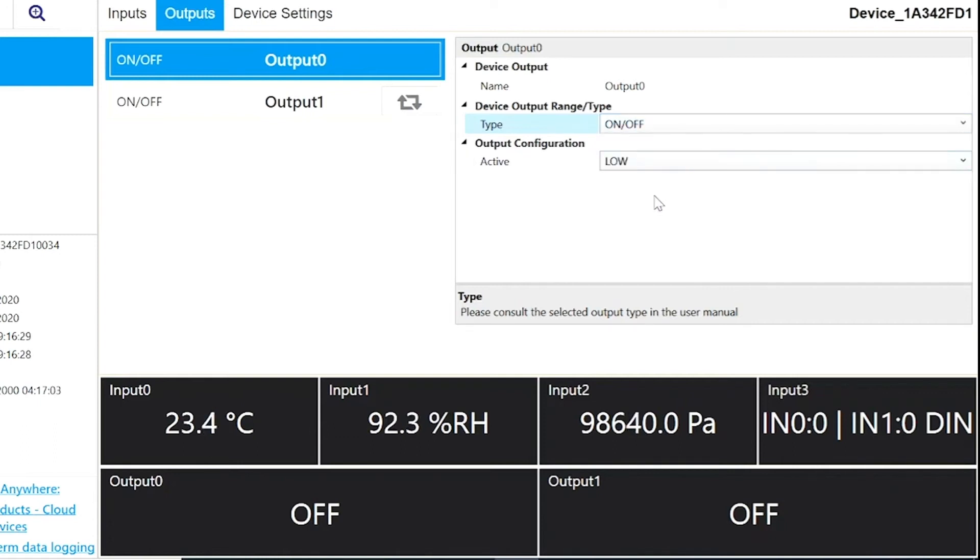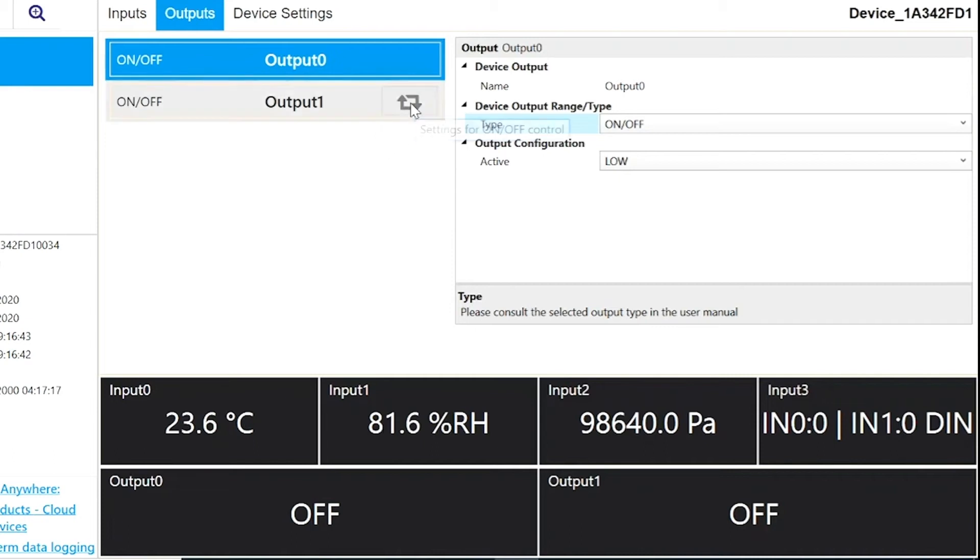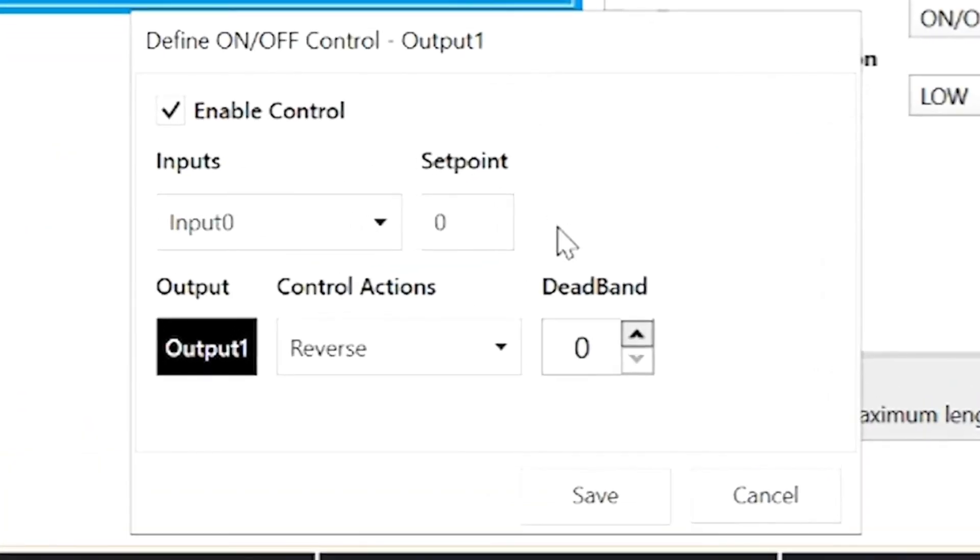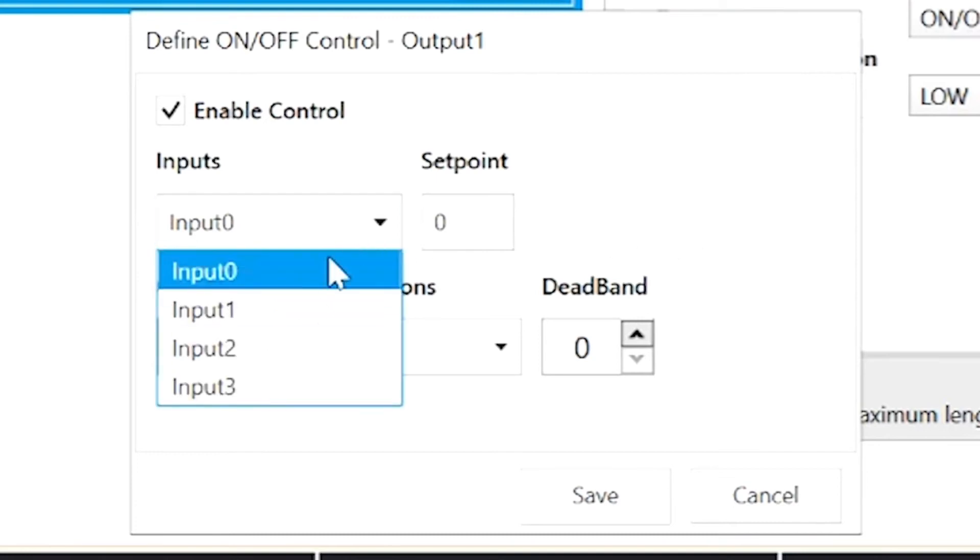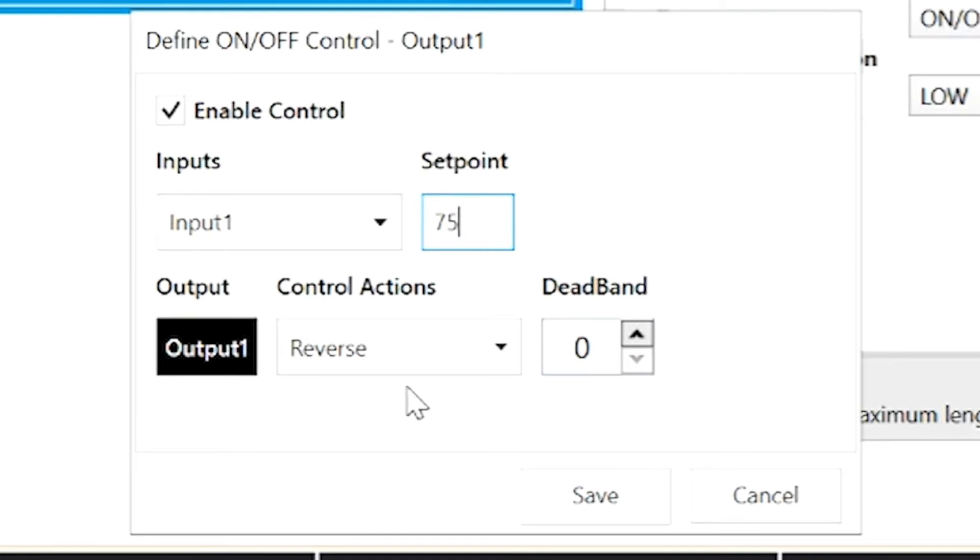the output can trigger a heater to switch off at a high temperature and switch back on at a lower temperature. We can see from the Output Configuration panel that Output 0 is already in use. But if we go to Output 1 here to the left of the panel and click on the settings for the On-Off Control button here, this will open the Define On-Off Control panel. Since our device can measure humidity, we'll set the input to Input 1 with a set point of 75%, and we'll leave the control actions at reverse, meaning the output will be on until the humidity hits 75%, and we'll leave the deadband at 0, and click Save.